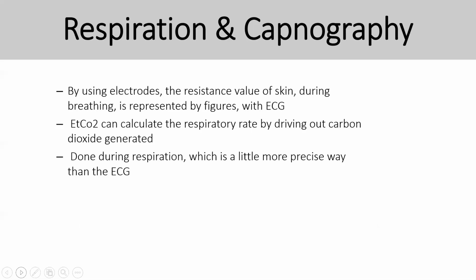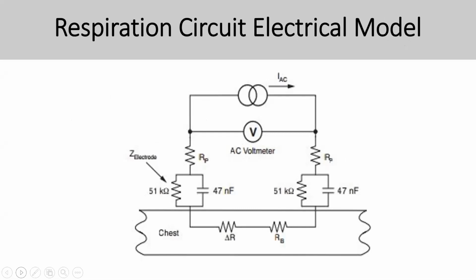Respiratory and capnograph is basically one of the things that you can see in two types of form. One is basically linked with the ECG. So the ECG system is basically going to measure between the electrodes the resistance value of the skin, the impedance. Based on that it is going to give you a respiratory reading. That's with the ECG. And another method is ETCO2, which can calculate respiratory rate by the carbon dioxide going to the module. From the module it is going to measure. That is more accurate compared to the ECG resistance impedance. So this is how the respiratory circuit electrical model looks like that works for ECG.